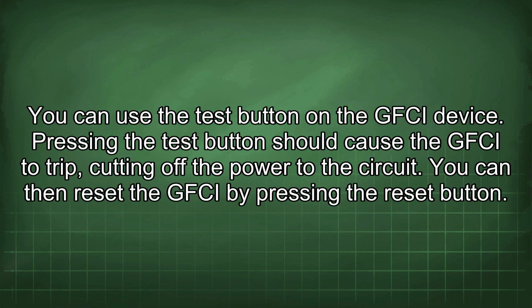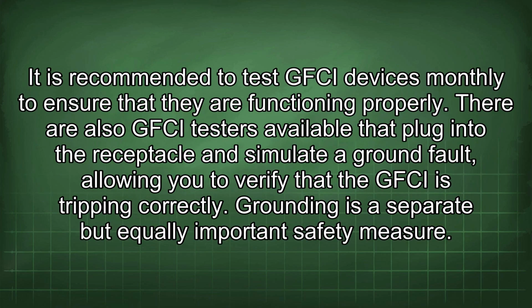Testing a GFCI is a simple process. You can use the test button on the GFCI device. Pressing the test button should cause the GFCI to trip, cutting off the power to the circuit. You can then reset the GFCI by pressing the reset button. It is recommended to test GFCI devices monthly to ensure that they are functioning properly. There are also GFCI testers available that plug into the receptacle and simulate a ground fault, allowing you to verify that the GFCI is tripping correctly.